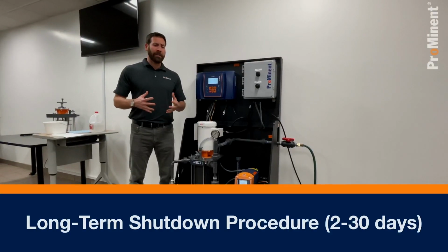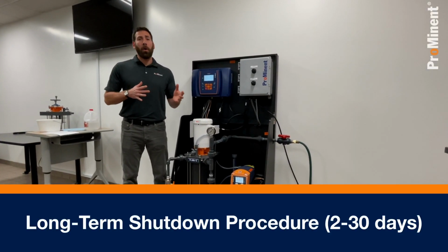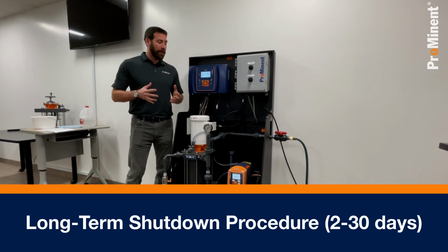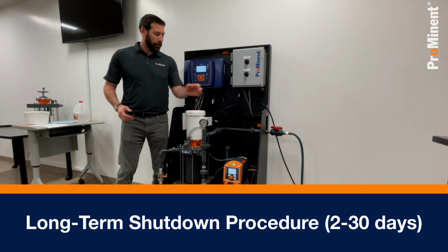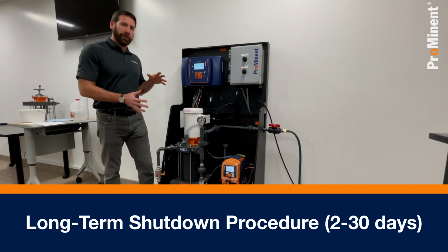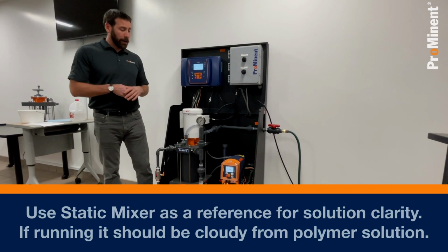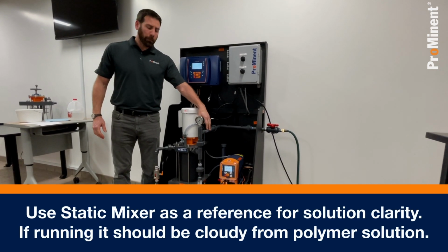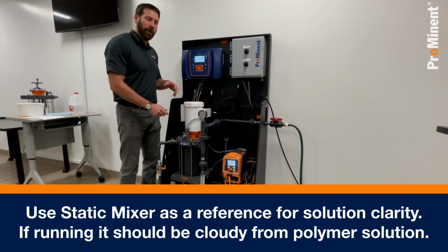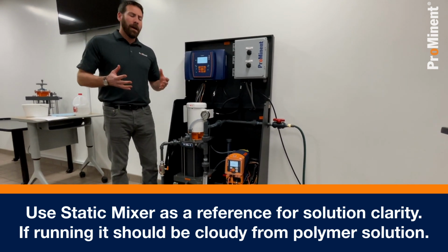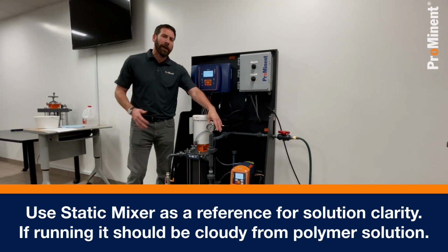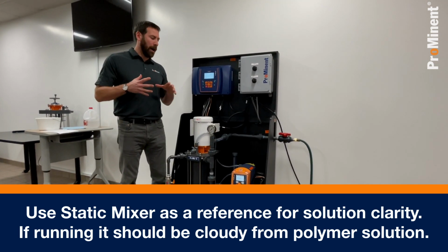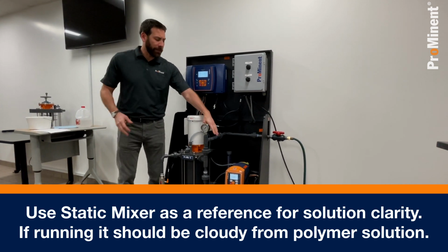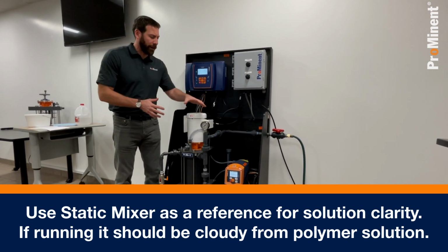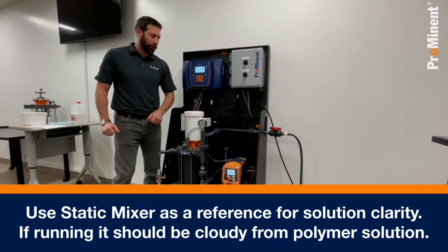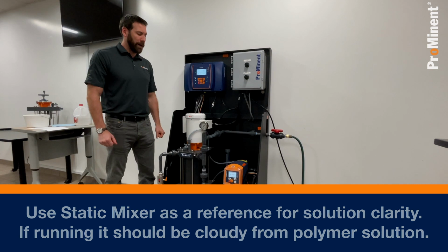For extended times of shutdown, which we would classify as 48 hours all the way to 30 days, we would recommend flushing out the polymer pump. So the first thing I need to do, our unit is currently running. If you're currently running, what I would reference is your static mixer. If you've been injecting polymer into your chamber, your static mixer is probably cloudy. At this point, I want to just visually reference what it looks like, because at the end of this cycle for extended shutdown, I want this to clear up. So right now I'm just visually referencing what that solution looks like going through my static mixer.